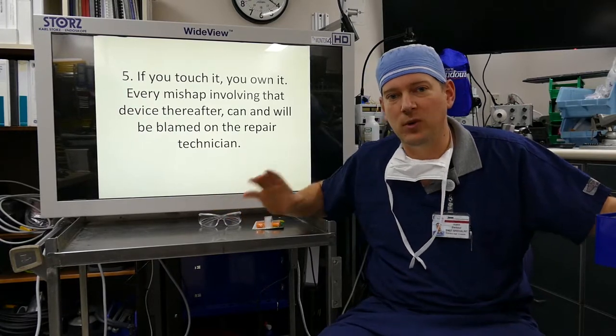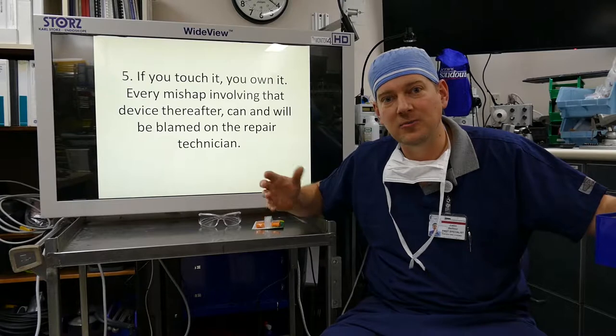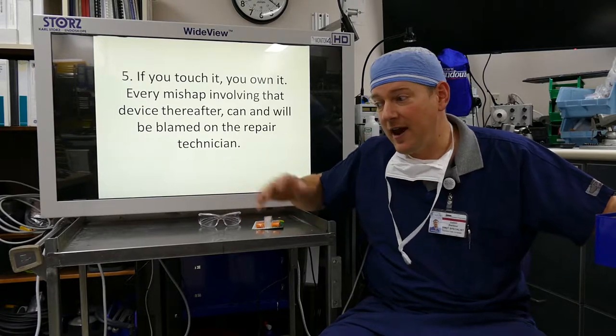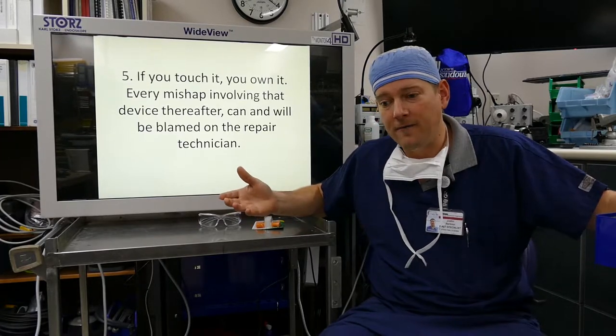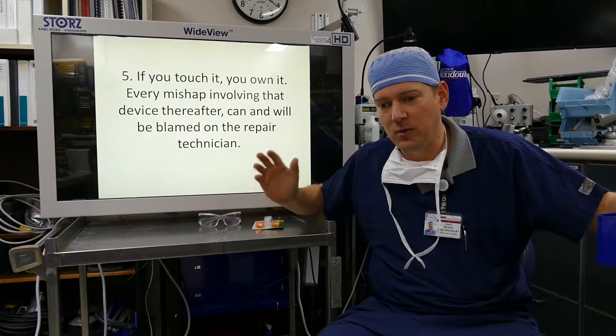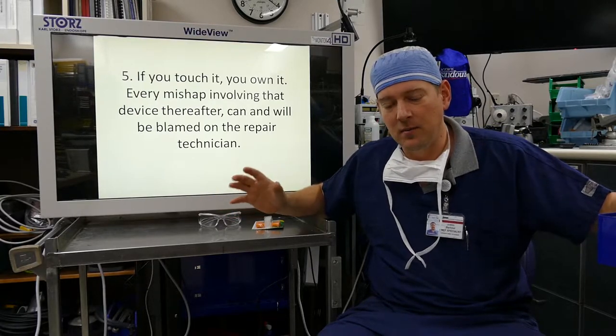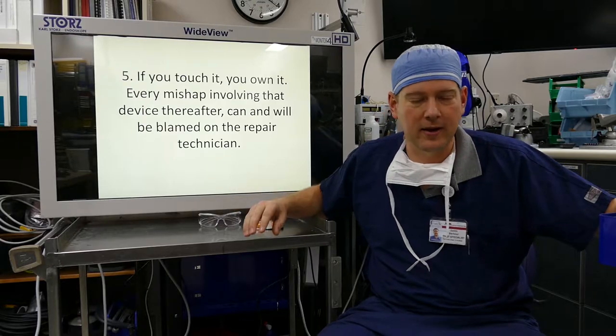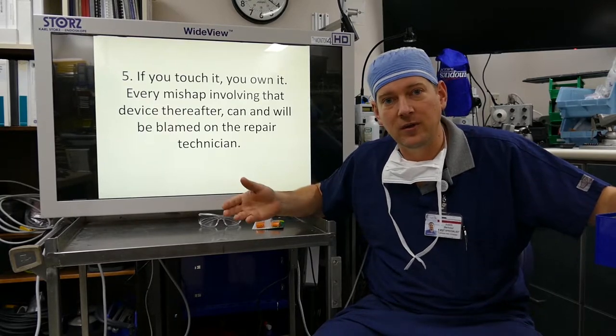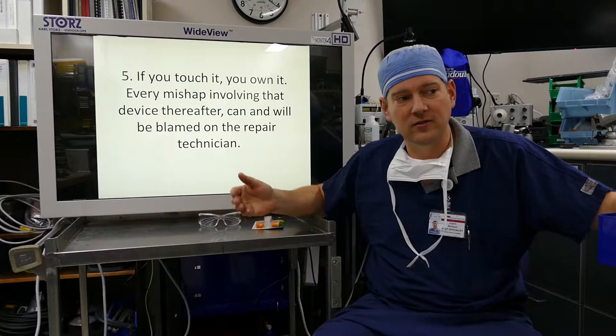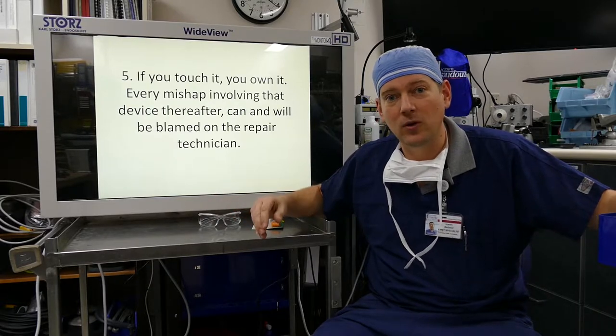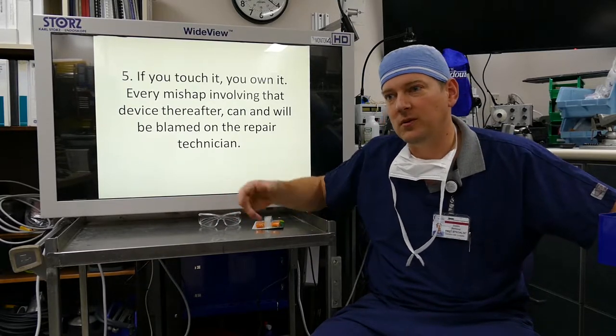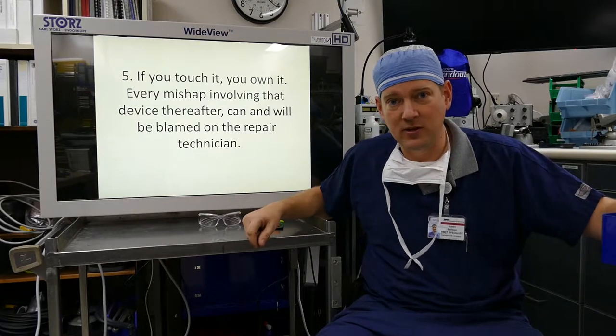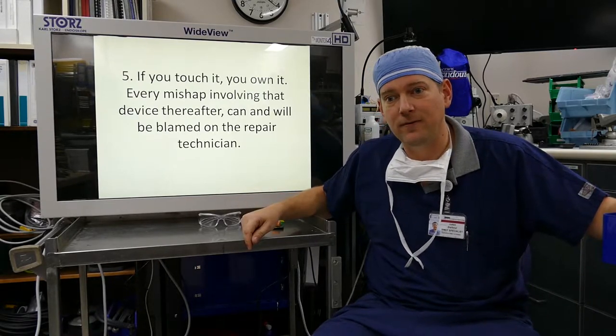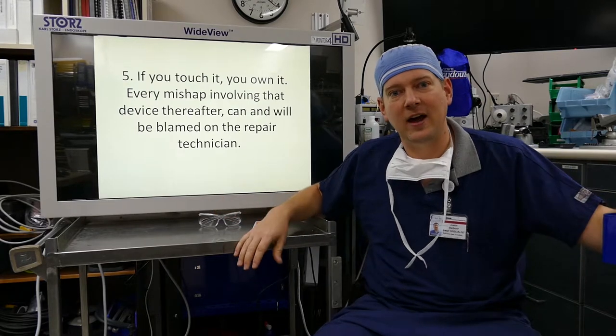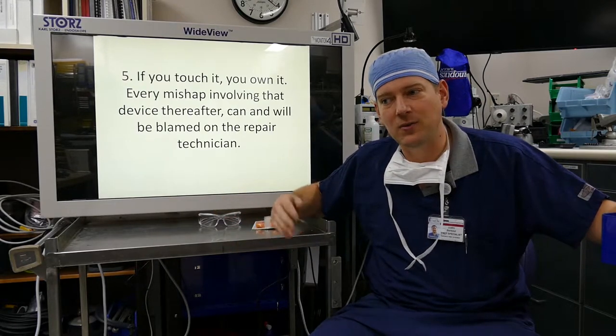The problem is, before you return it to service, you need to inspect everything and make sure every piece of it is ready to go. Too often people show up to a piece of equipment, do the bare minimum just to get it back into service, and put it back into service. That's lovely, except we take care of people, and a lot of these devices keep people alive. So you have to check out everything before you return it to service. If it can be blamed on you, it will be. Protect yourself and protect the patients, fix everything on it that you can possibly fix, and then return it to service.